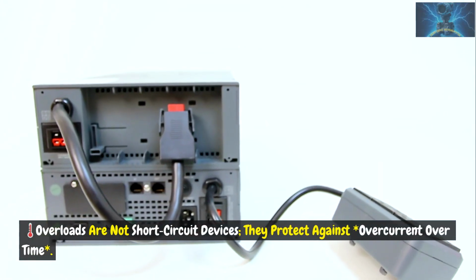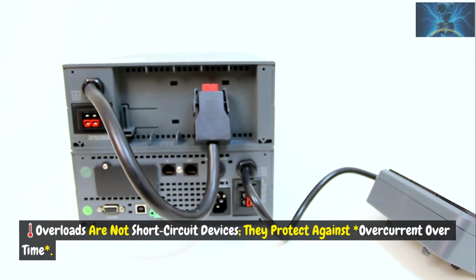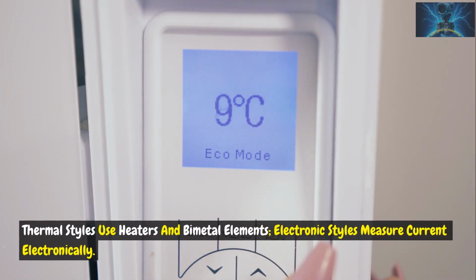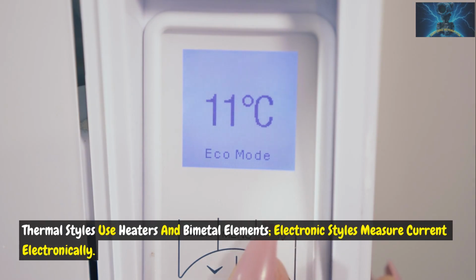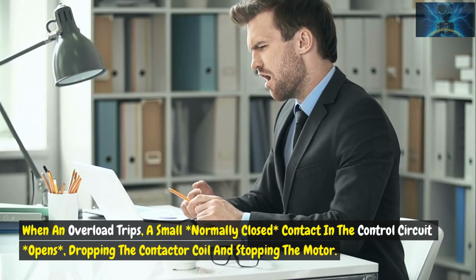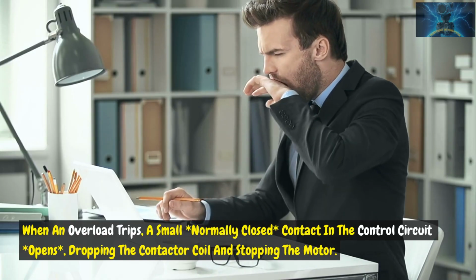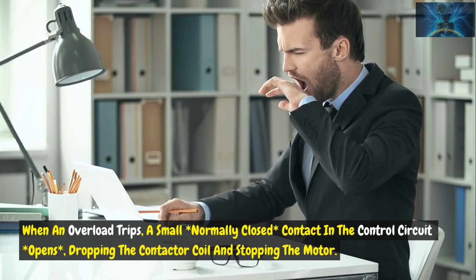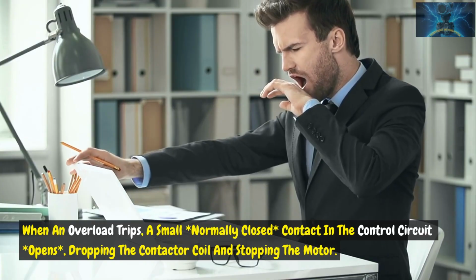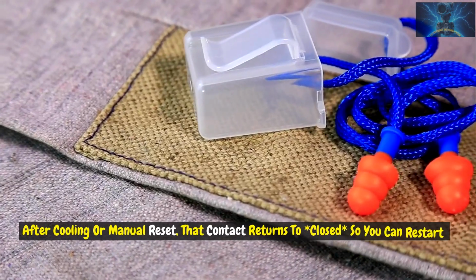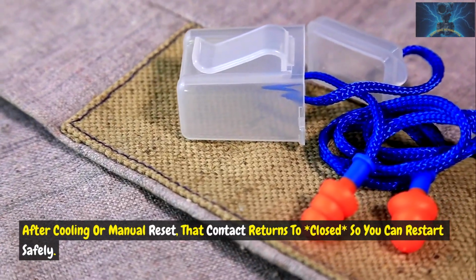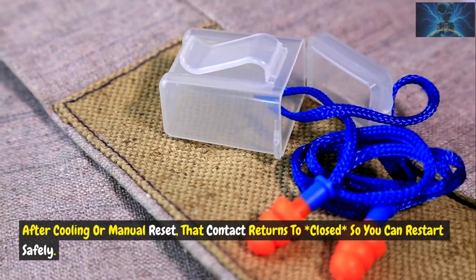Overload relays, saving the motor from heat. Overloads are not short-circuit devices. They protect against overcurrent over time. Thermal styles use heaters and bimetal elements. Electronic styles measure current electronically. When an overload trips, a small, normally closed contact in the control circuit opens, dropping the contactor coil and stopping the motor. After cooling or manual reset, that contact returns to closed, so you can restart safely.